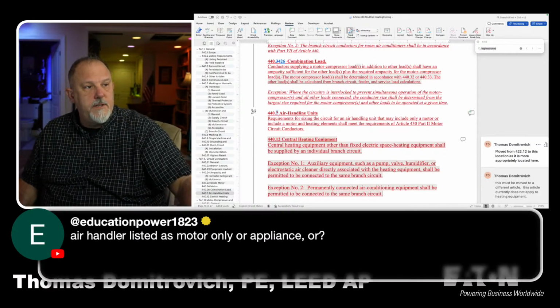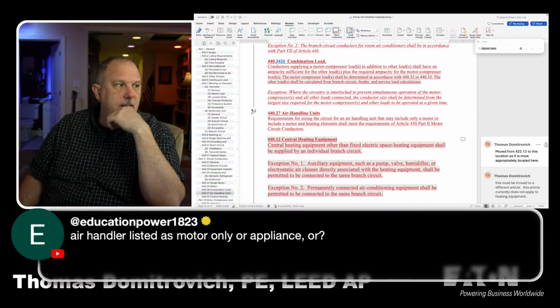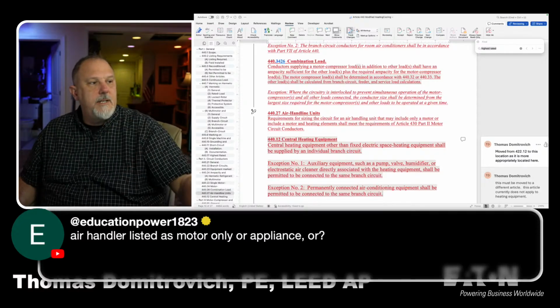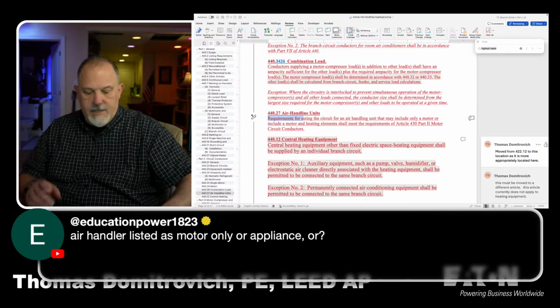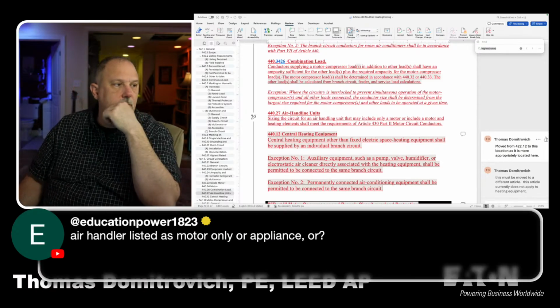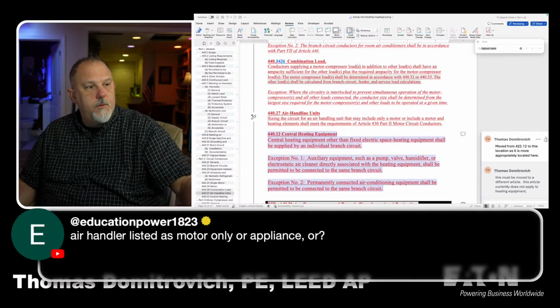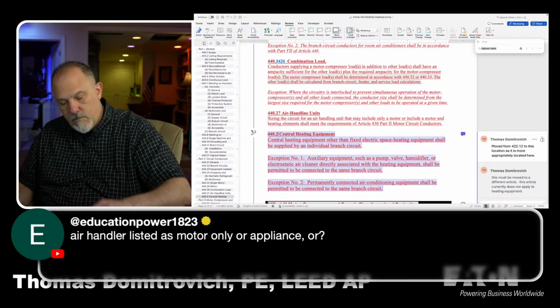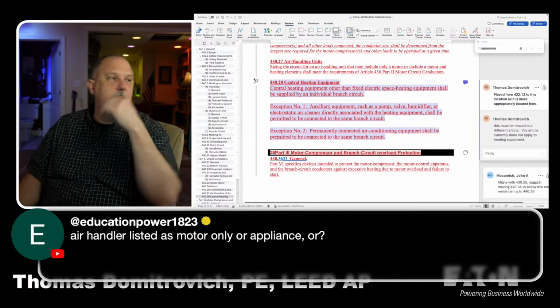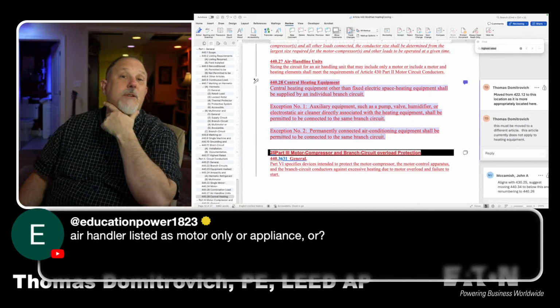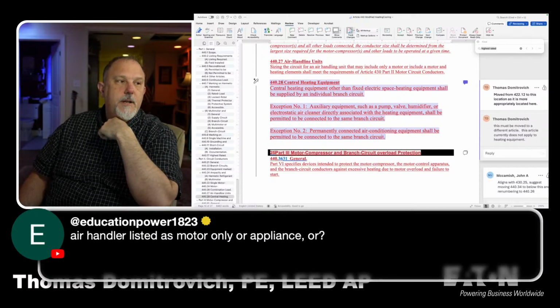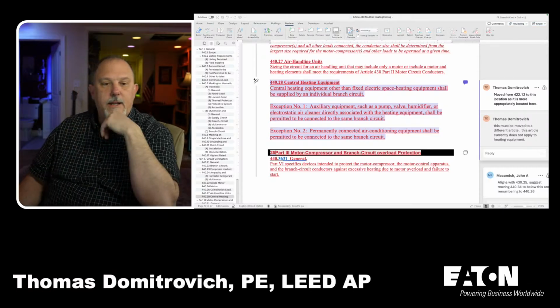We'll make this 440.27. Requirements for sizing the circuit for an air handling unit that may include only a motor or include a motor and heating elements shall meet the requirements of Article 430 Part 2 motor circuit conductors. Central heating equipment, this is from 422.12. We'll call this 440.28. Central heating equipment other than fixed electric heating equipment shall be supplied by an individual branch circuit.